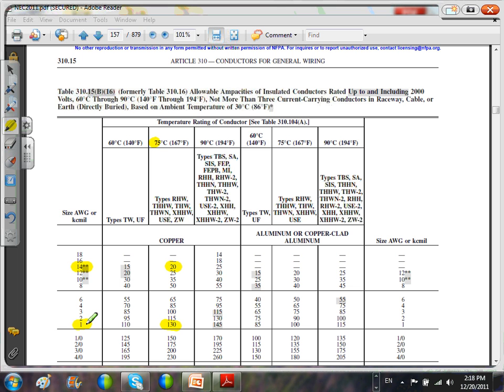And by the way, if you haven't seen this, this is the copper area. And remember, we're engineers, we don't buy the equipment, we design it, so we're always sizing this on copper. But aluminum is good. If you want to size this on aluminum, you're going to go to this side. For the same application, if we're using aluminum, we're going to use 20 here. I need a 20, that will give you number 10 aluminum. God forbid if you're using aluminum.